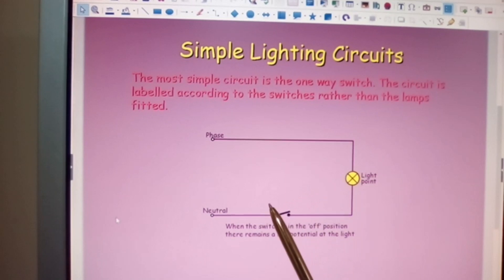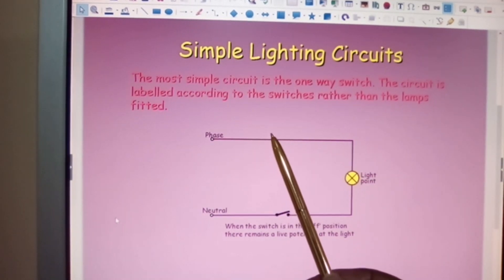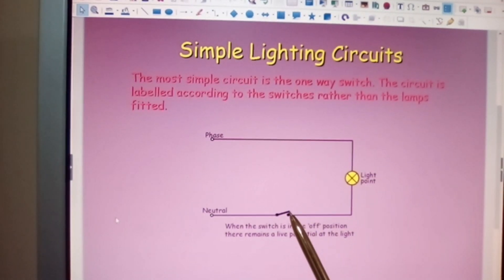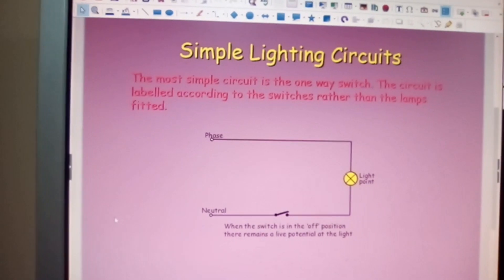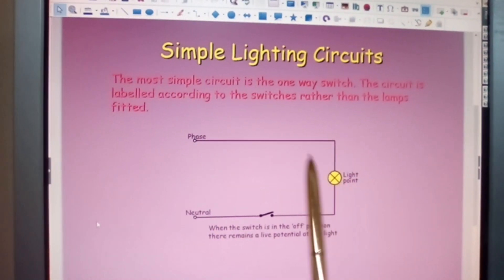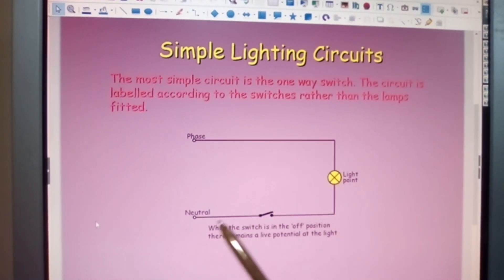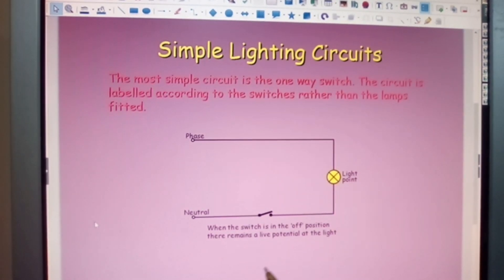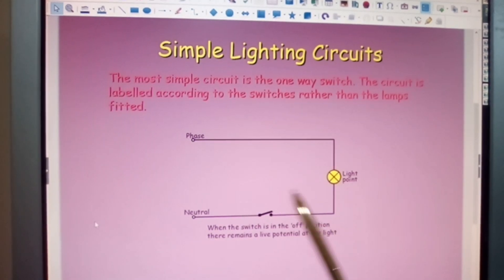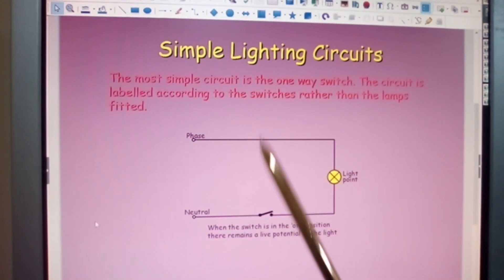So you will not wire a light like this. The switch should always be in the phase conductor, not the neutral. Now I don't know why they've done it this way, but it's possible somebody trying to illustrate a point. So the switch always in the phase conductor.